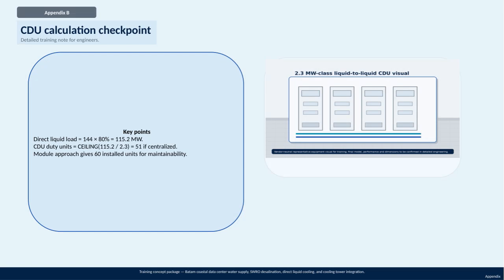Here in Appendix B, we focus on the CDU calculation checkpoint, which is essential for our engineers' detailed training. The training concept package covers critical systems for the Batam Coastal Data Center, including the water supply, SWRO desalination, direct liquid cooling, and the integration with cooling towers. One of the key points is a calculation of the direct liquid load, which comes out to 144 megawatts multiplied by 80%, giving us 115.2 megawatts.